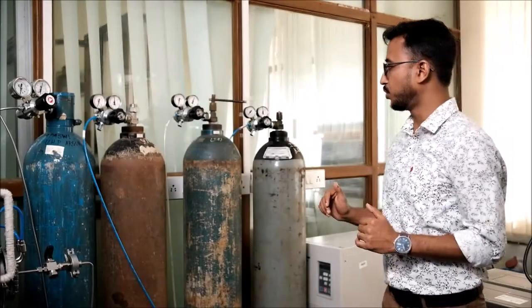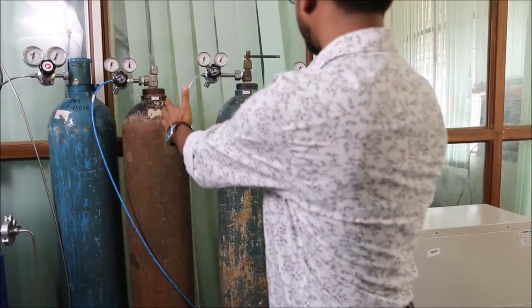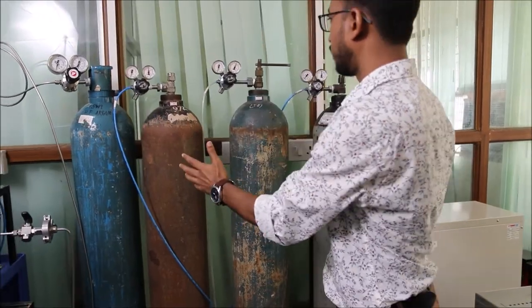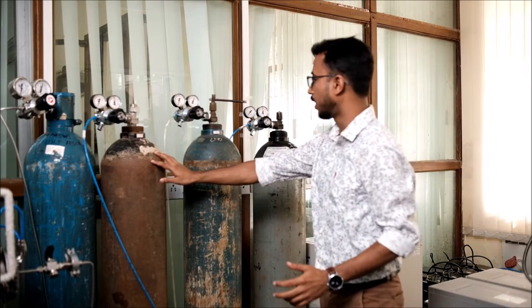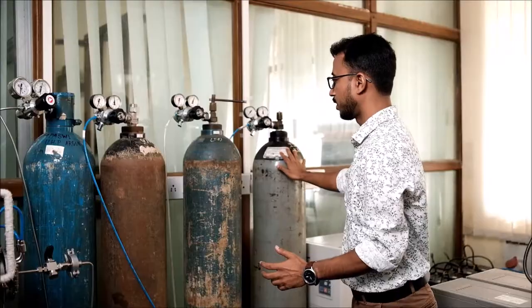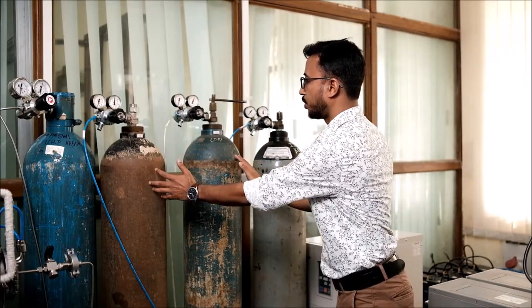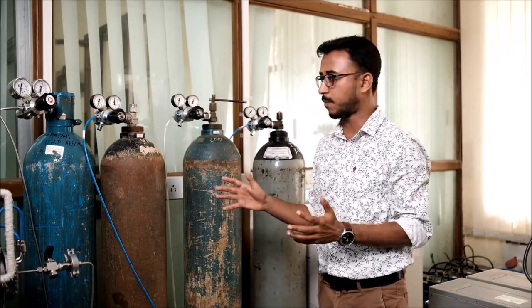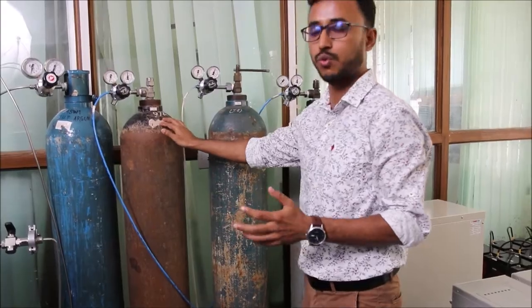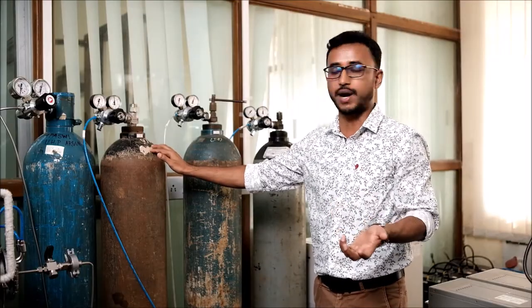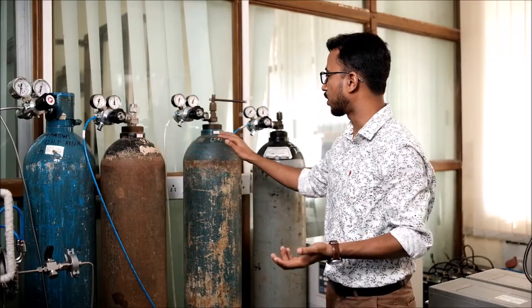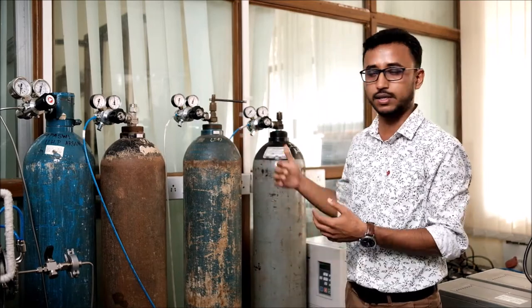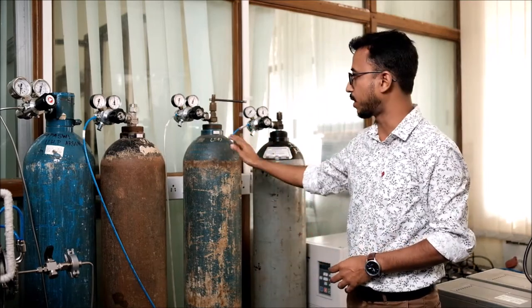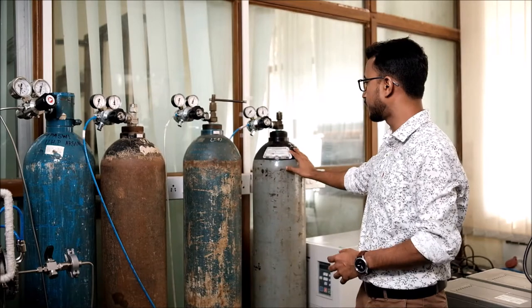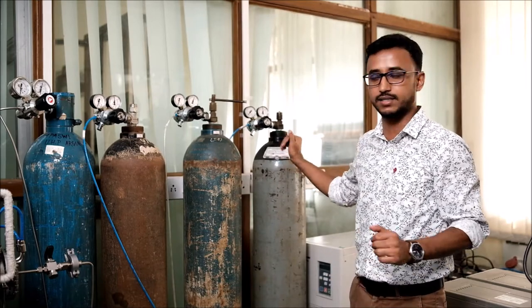So in the gas unit system, we have three cylinders for three different gases. One is the oxygen, and then the argon, and then the nitrogen gas. So these two gases we use for the actual deposition system. Oxygen is used while doing a reactive sputtering deposition, and argon is required to sputter the system. So we have to always supply the argon gas. And this nitrogen gas, we use it for venting the system.